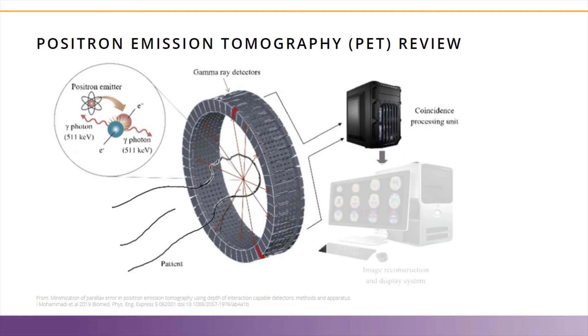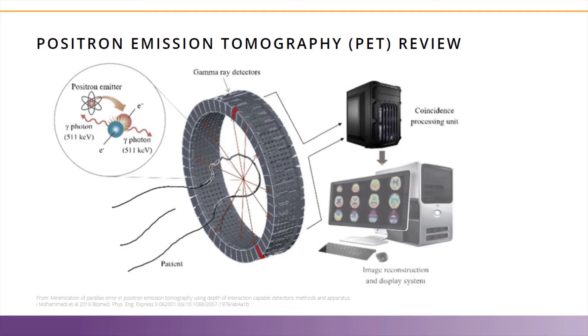These detectors send a signal to the electronics when they detect a gamma photon with a specific energy related to the isotope. The electronics are programmed to determine which gamma rays were detected in coincidence — those sensed by opposing gamma ray detectors at the same time. The electronics then form a line of response, or LOR, between the coincidence gamma rays, and use this information from all detected coincidence events to reconstruct an image, providing spatial information about the location of the radioisotope and quantifiable measures of concentration based on the counts.